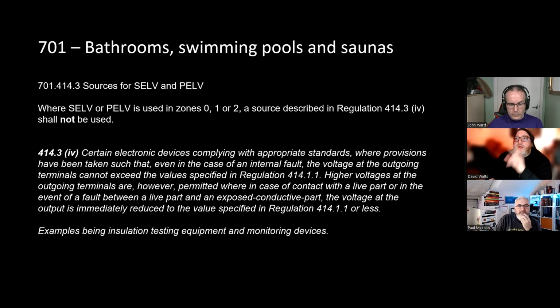Anyway, right. This is 701.414.3, which identifies that when we have SELV and PELV as a protective function, one of the methods of achieving SELV or PELV is 414.3, and that uses electronics, basically. There's a quote of it there: certain devices comply with the appropriate standard where provisions are taken such that in the event of an internal fault, the voltage on the outgoing terminals cannot exceed the value specified in 414.1.1, which is obviously SELV or PELV. High voltages at those outgoing terminals can be permitted in such cases, though.